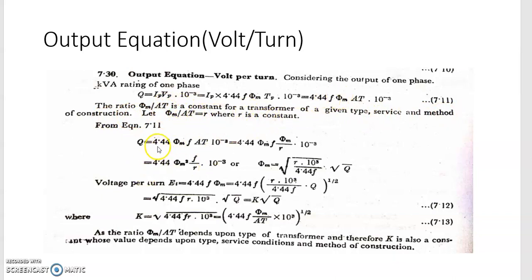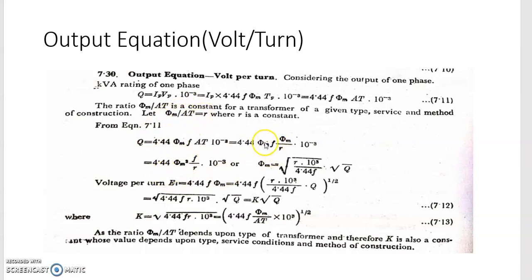Taking the equation KVA = 4.44 × phi_M × f × AT × 10⁻³, and since phi_M / AT = r, we replace AT by phi_M / r. This gives us phi_M squared. So phi_M × phi_M / r leads to the main equation. We need to find phi_M — the maximum flux — which equals the square root of (r × KVA × 10³) / (4.44 × f).